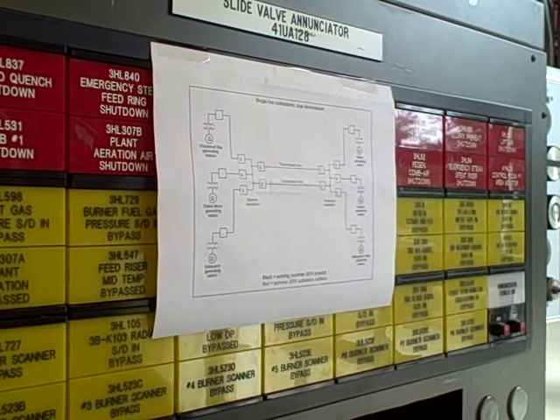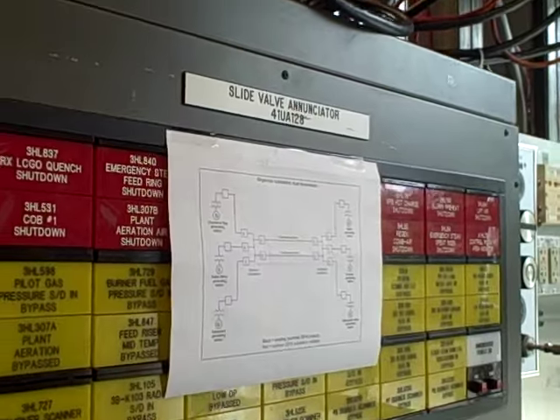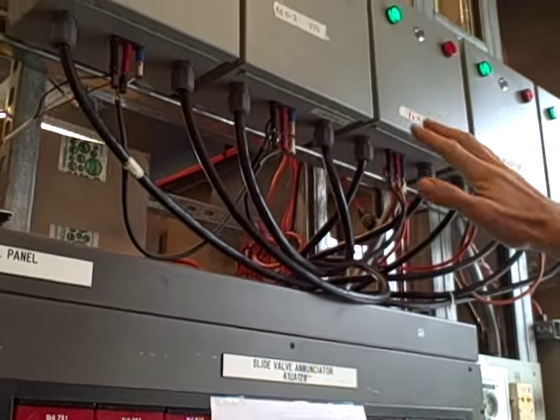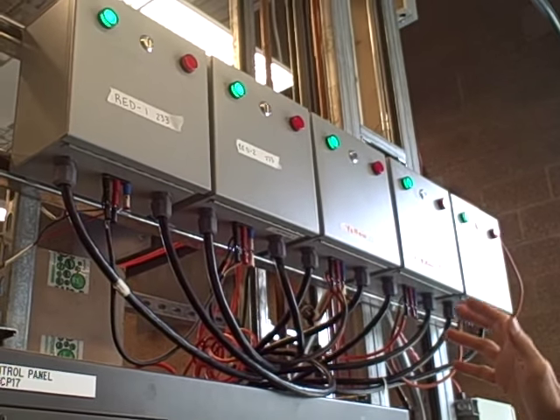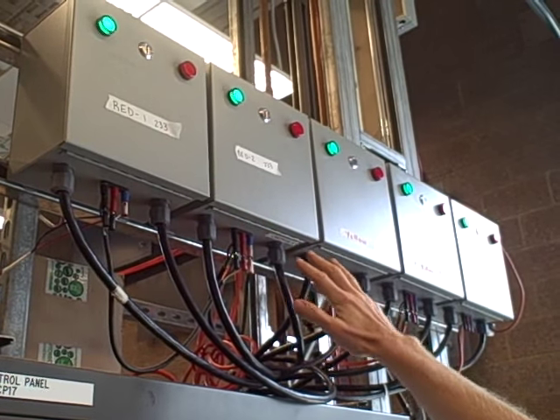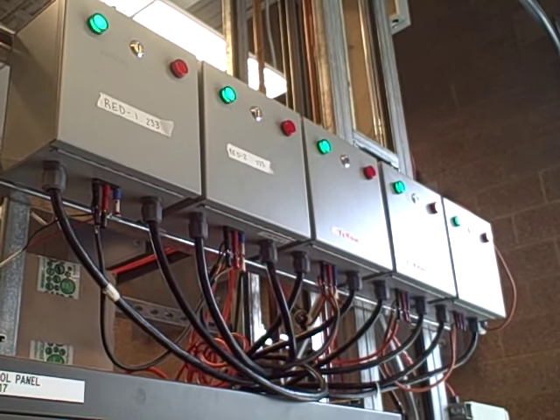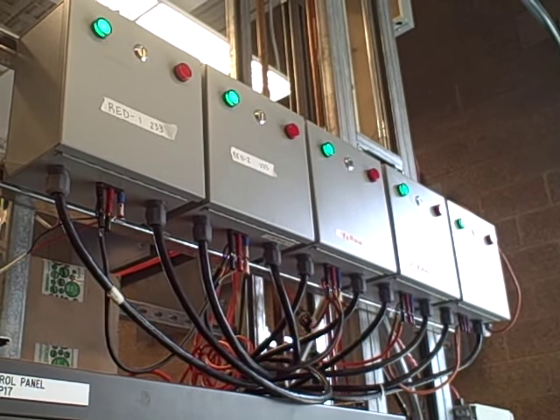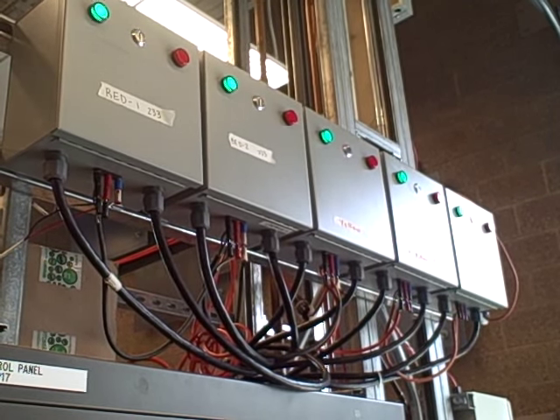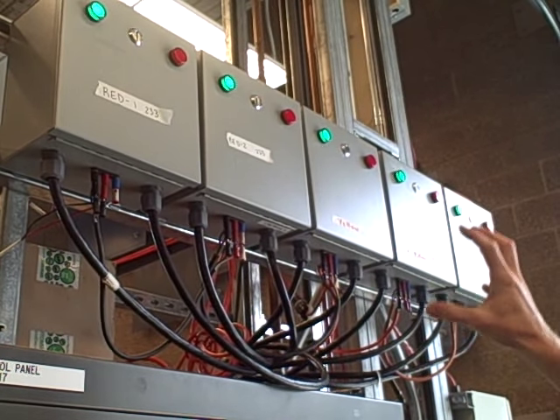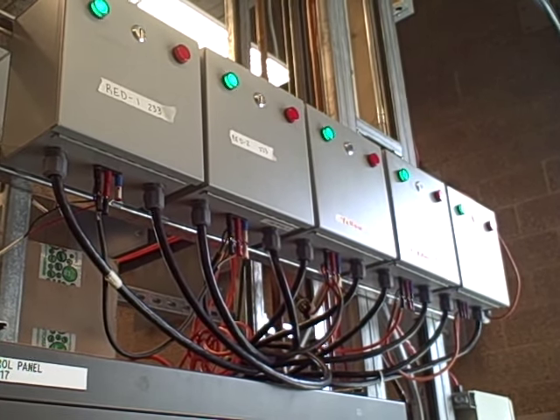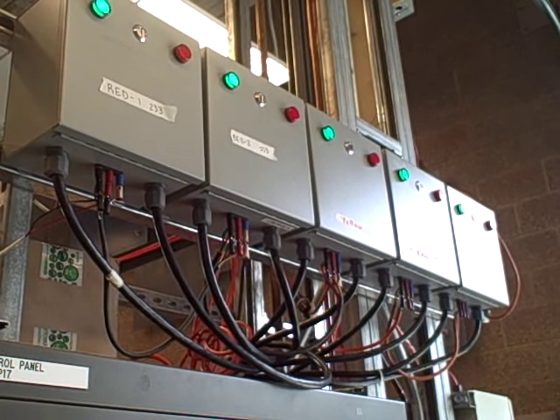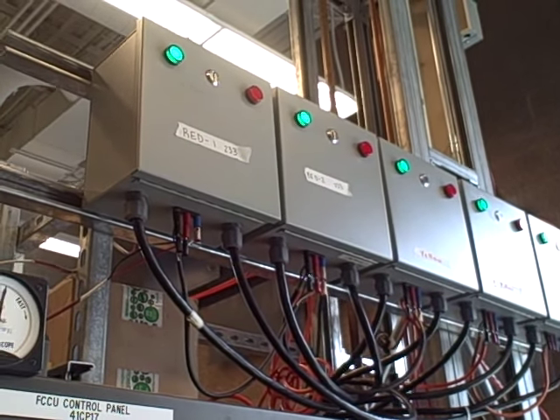And what we do there, we can see above here, are our circuit breakers. We have five of these circuit breakers. We had to build these breakers ourselves using 10x10 enclosures. Inside of each enclosure is a three-phase power contactor like you might use to start a motor. And we have some relay circuitry wired up to it so it acts as a latching circuit breaker.